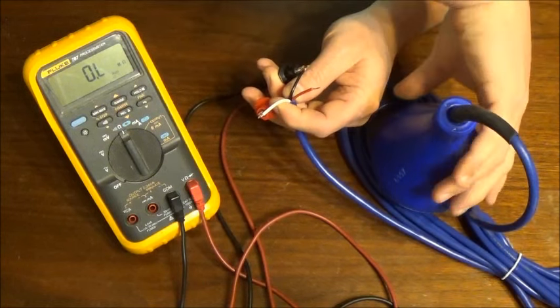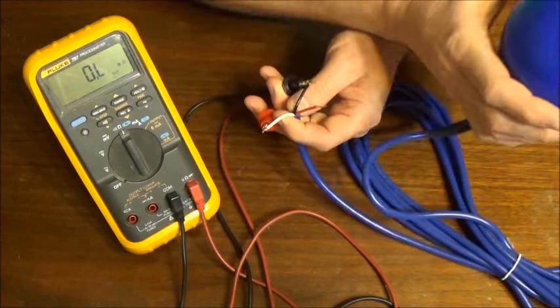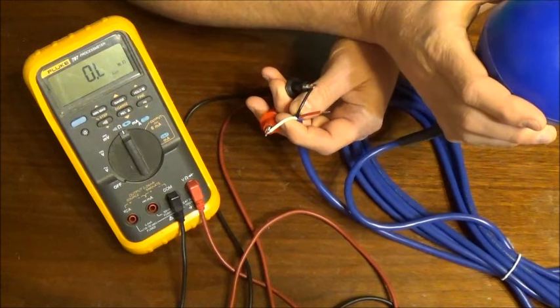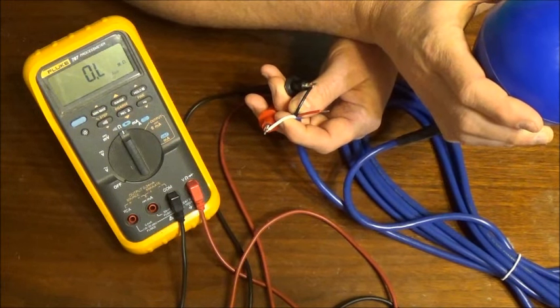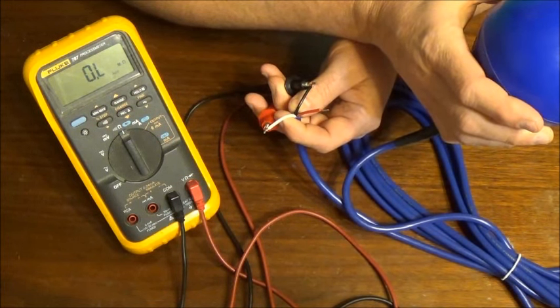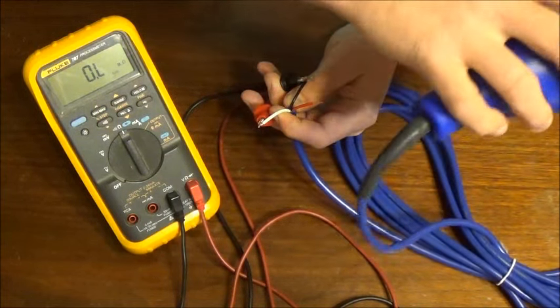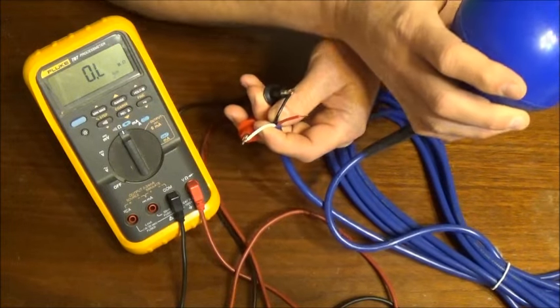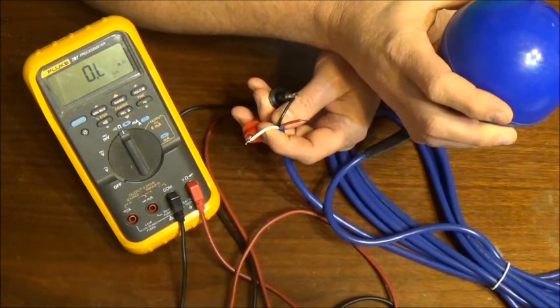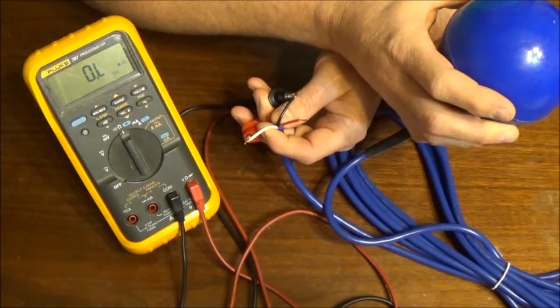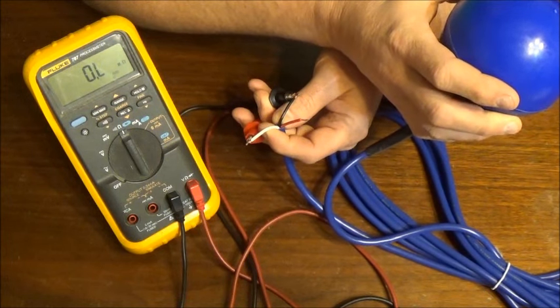If we toggle the float to what should be the opposite condition, that state should change to a short. As you can see, you can hear the switch toggling. This meter is reading the same either way, indicating that the float switch is bad.